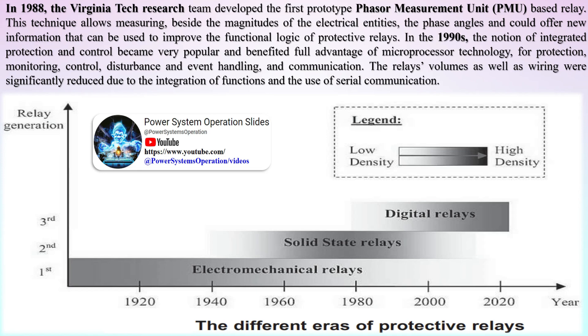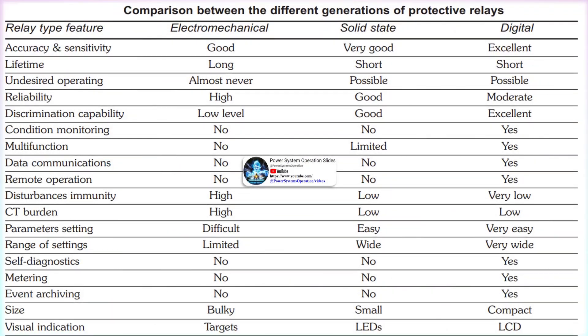It is the job of power system protective equipment to detect the onset of undesired events and take appropriate action. Appropriate action often includes the tripping of circuit breakers, which isolates the trouble from the remainder of the power system and minimizes damage. Relays can be broken down into a few major classifications: monitoring relays such as high temperature or gas and oil relays, which monitor power system quantities and initiate an alarm if those quantities are outside set limits; auxiliary relays such as timers, tripping, reclosing, or lockout relays, whose job is to supplement the actions of other relays; and programming relays such as automatic synchronizers and generator auto-start relays, which go through a sequence of programmed steps to complete an operation.